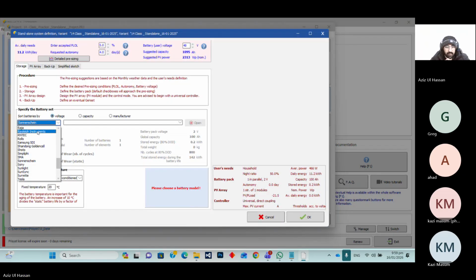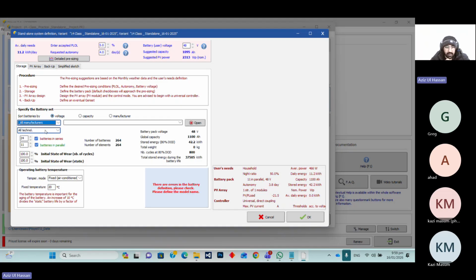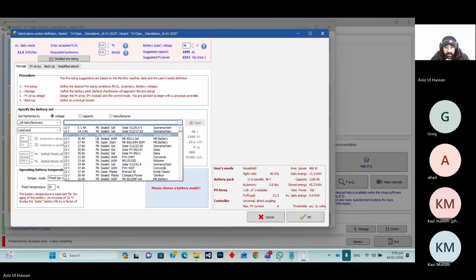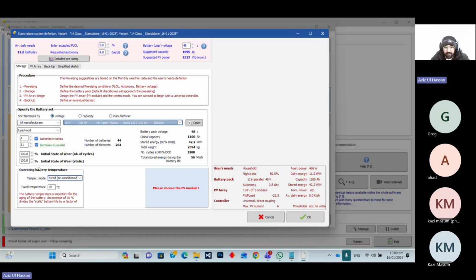We have to select all manufacturers. Lithium ion, like we have lead acid batteries. On voltage basis, you have to select that one. Like we have 100 ampere hour, 12 volt batteries. We have selected four batteries in series and 11 in parallel. So the pack voltage becomes 48, the global capacity becomes 1100 ampere hours, the usable capacity at 80% is 42.2 kilowatt hours, and the total weight is this many kg. They have the cycles.